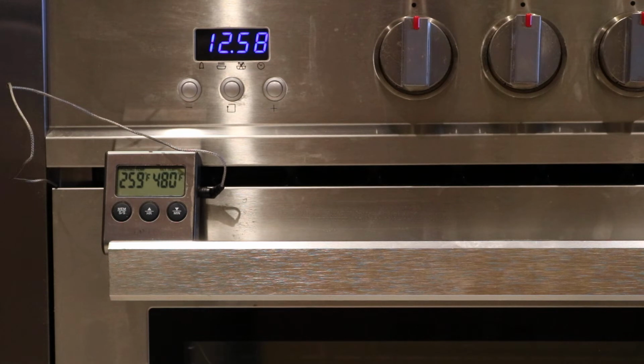It didn't turn off — temperature's rising again. It's almost as if the thermostat thinks it's set for 270 degrees instead of 480 degrees Fahrenheit. The analog thermometer is starting to rise too, but it has a slower response. Eventually they'll get to the same temperature.